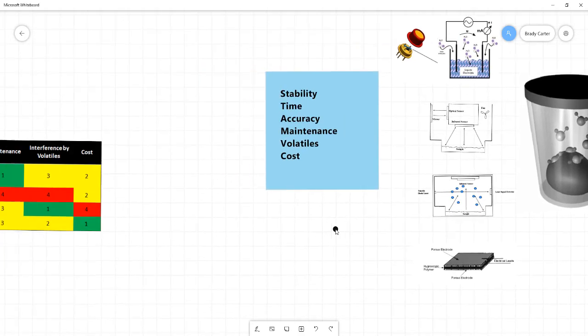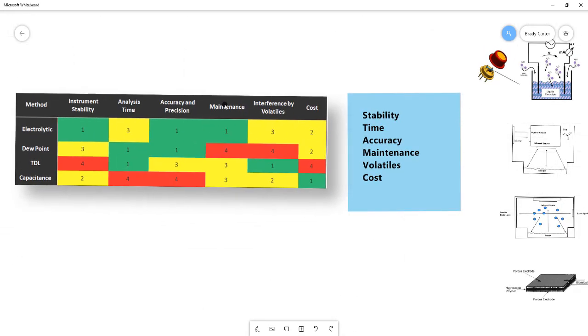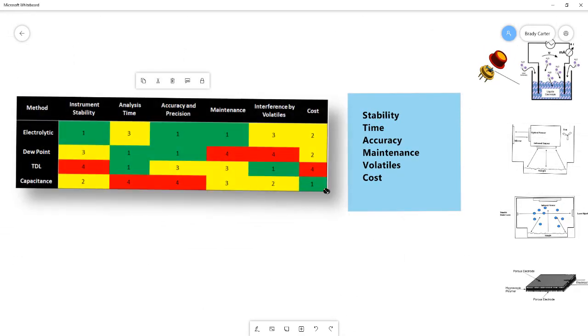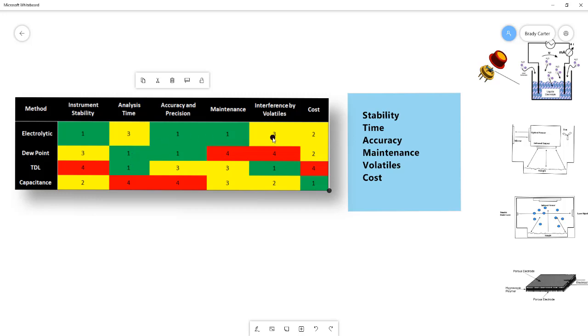So if we consider all of those factors now, and we take our discussion and put it in terms of a table, what we see is each of these methods and where their positives and where their negatives are. So for the electrolytic sensor, stability is a very high positive as well as accuracy and precision and maintenance because of its tendency to not be affected by contamination, but it's a slower analysis time. It will always be slower than the dew point and TDL and it is susceptible to volatiles. Meanwhile, the dew point gets high rankings for analysis time, fastest method, very accurate as long as it's maintained, but the high level of maintenance required and the fact that certain volatiles, it cannot read at all, are the negatives for that particular method.